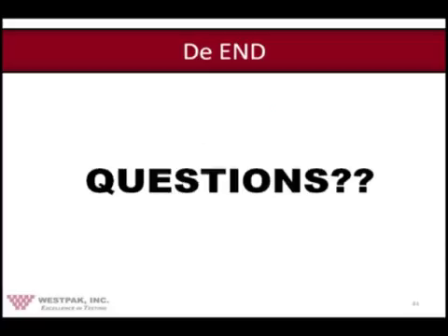Let's see if I can understand the question. Does it apply to non-sterile products? And the answer is yes. There is no requirement in the Arrhenius equation or in the derivation of it in ISO 11607 or ASTM F1980 that would say that anything reacts differently whether sterilized or not sterilized. Okay, so sterilization has no effect on the aging rate at all. Okay, any other questions, Greg?